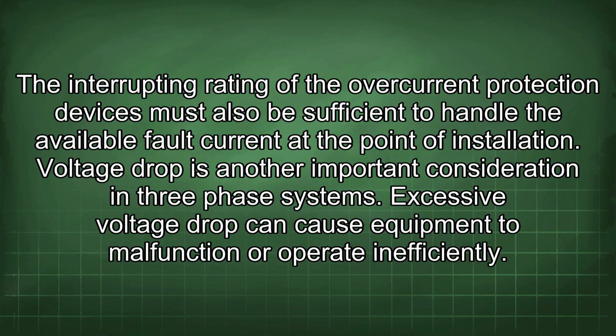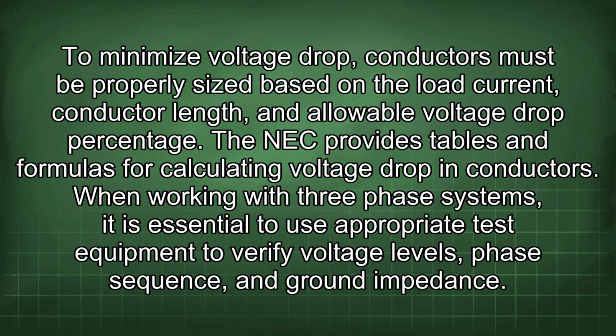Voltage drop is another important consideration in three-phase systems. Excessive voltage drop can cause equipment to malfunction or operate inefficiently. To minimize voltage drop, conductors must be properly sized based on the load current, conductor length, and allowable voltage drop percentage. The NEC provides tables and formulas for calculating voltage drop in conductors.